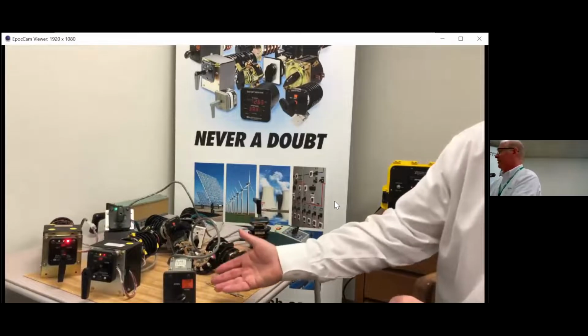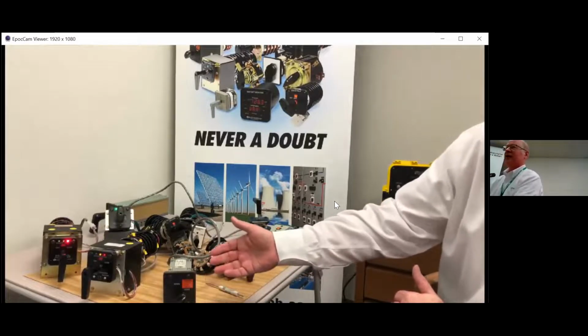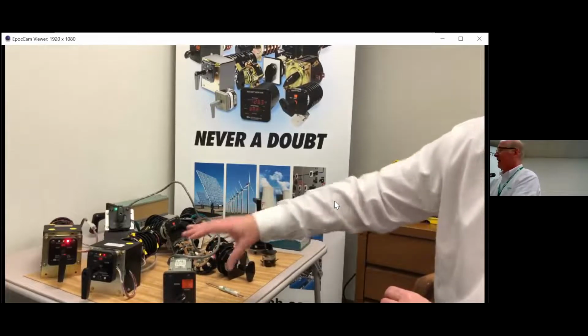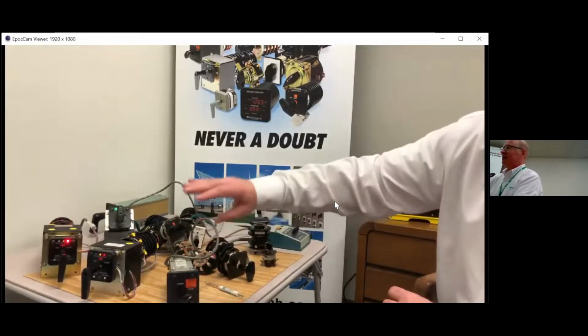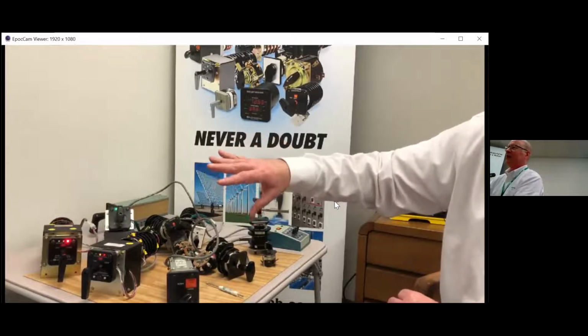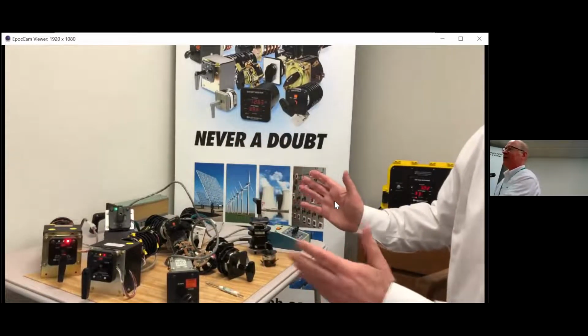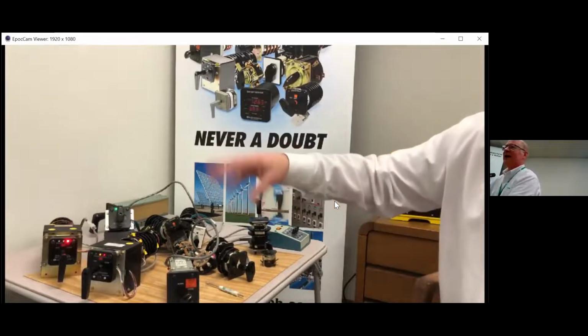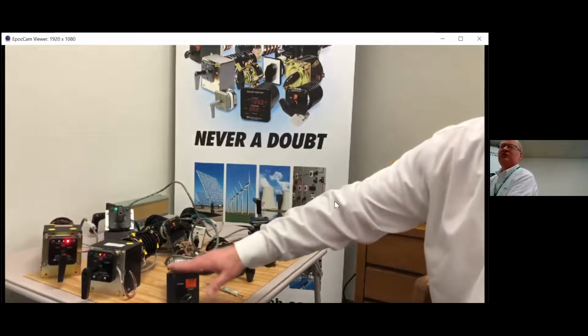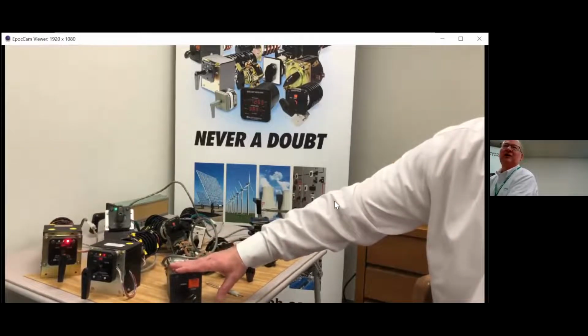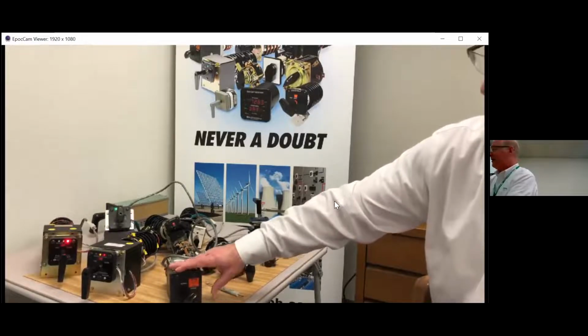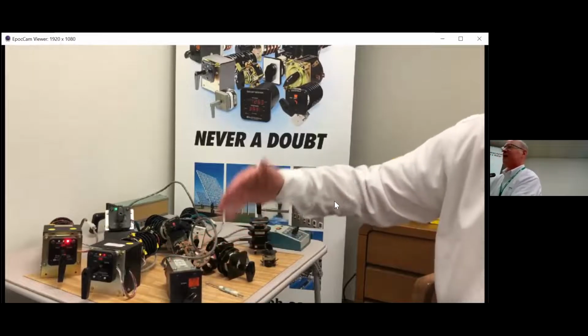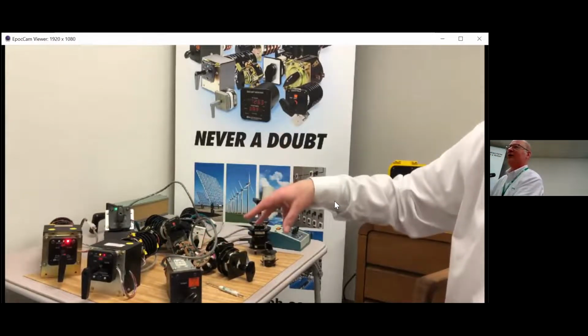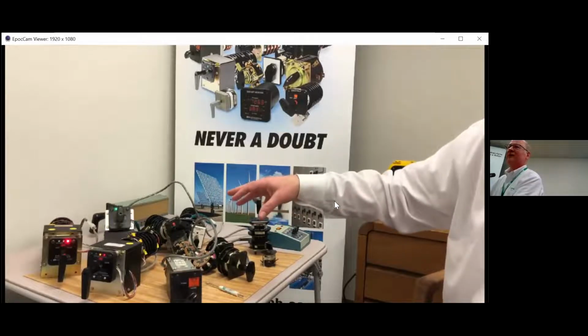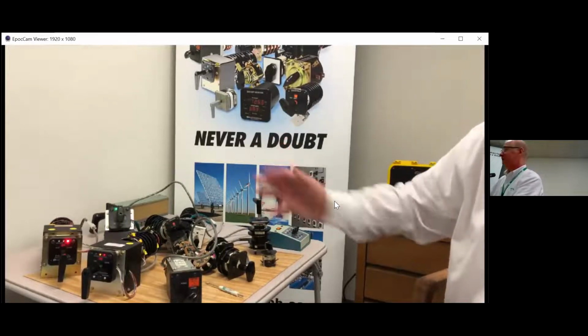I also just had an application yesterday where a customer was looking at applying a lockout relay to tell their operators and their people that on a double-ended substation, I have a tiebreaker that is tied or untied. And so they use this as a tied and untied function that will allow them to inform people through SCADA as well as at the switch that a double-ended substation has its tiebreaker closed or open. If it's closed, that means it's tied. If it's open, it's untied.